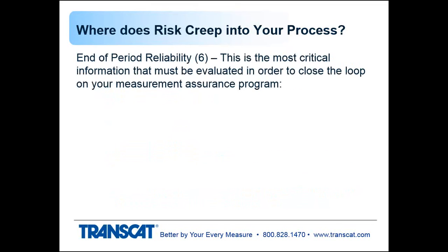And then end-of-period reliability, which is the most critical information that assesses the status of the instrument and tells you whether or not the decisions you've been making with that instrument were good or bad. If the instrument was found out of tolerance, then obviously you've got some evaluation to do to determine whether those out-of-tolerance readings impacted your decisions.